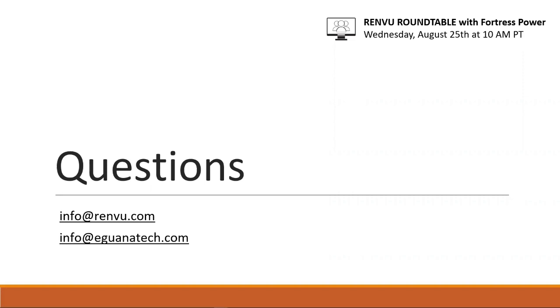Another attendee mentioned that they thought Enphase and other microinverters can respond to phase shift commands and be scaled back to the 5 kW limit for off-grid AC coupled PV systems. Yes, while it is true that the frequency watt functionality of the battery can be used to vary the phase and the frequency, and that PV inverters will respond accordingly, how much they will derate and how fast, I may have to get back to you on this, but I believe it's proprietary.